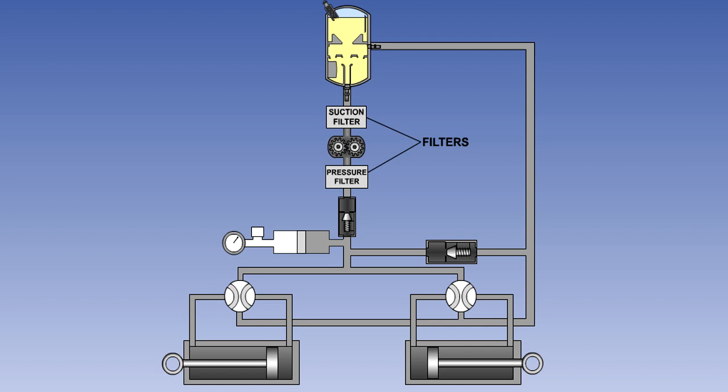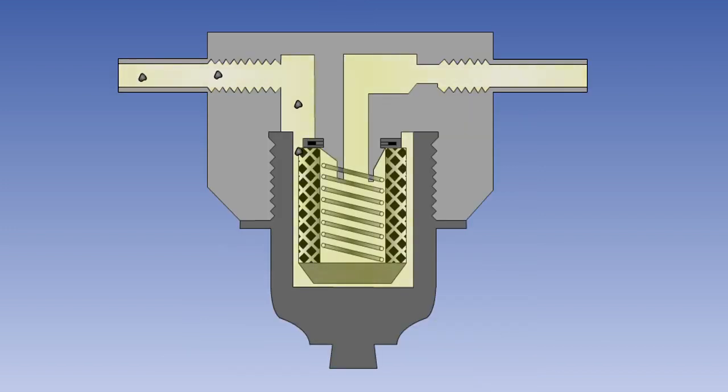The suction filter protects the pump, and the pressure filter ensures the cleanliness of the hydraulic fluid during use. There is also sometimes a filter fitted in the fluid return line to the reservoir, to remove particles picked up during component operation. Filters remove foreign particles from the fluid, thus protecting the seals and working surfaces of the components.